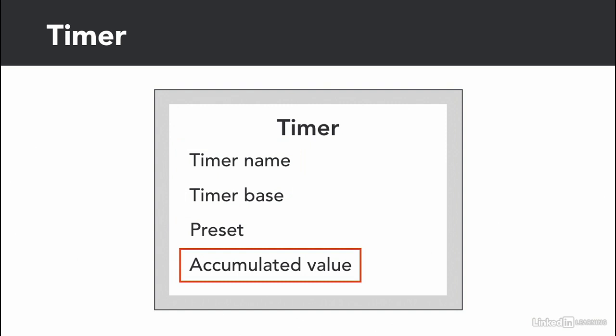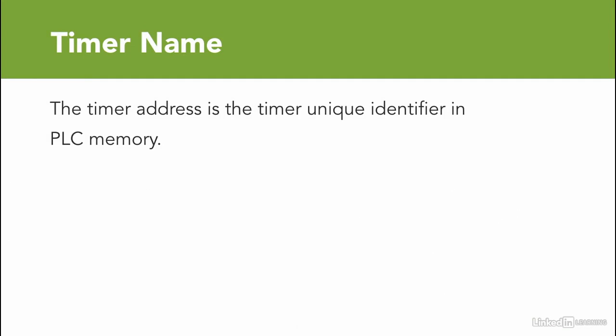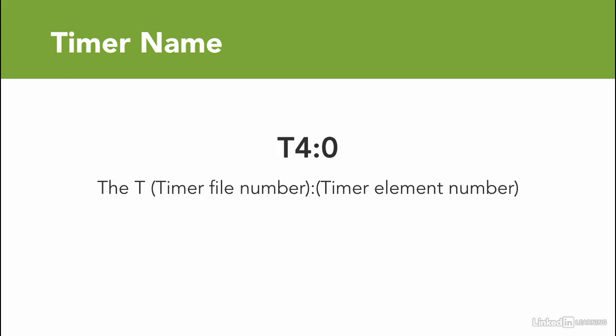Let's see what each part is. A timer name is the timer unique identifier in the PLC memory. No matter what brand of PLC, each timer will have a name or a number to identify it. Depending on the PLC type, there is a certain way to write the name. An example is one of the Allen Bradley PLC address is T4:0. T, then the timer file number, and finally the timer element number. So T4:0 is timer file 4, timer element 0.